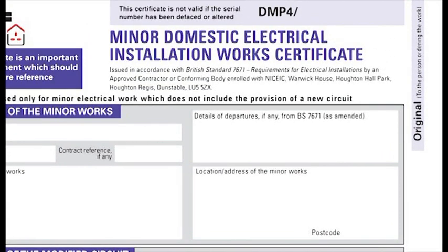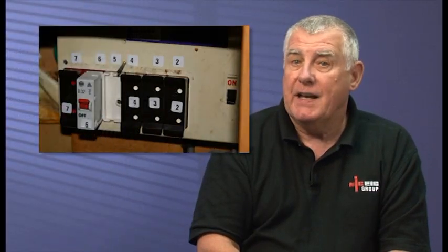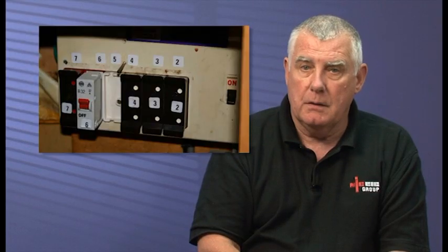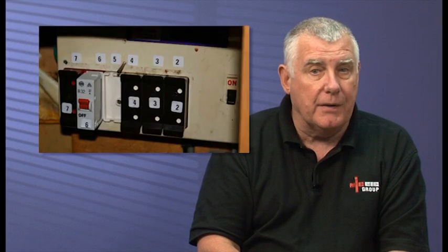The first is details of departures, if any, from BS 7671. Sometimes it is thought that this is always referring to departures in the existing electrical installation. This may be the case, for example, where a circuit protection device is manufactured to BS 3871, which is a standard no longer recognised by the current regs. But its use is also for situations such as where possible non-British or European standard equipment is being installed as part of the work.